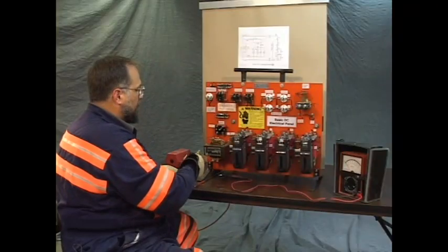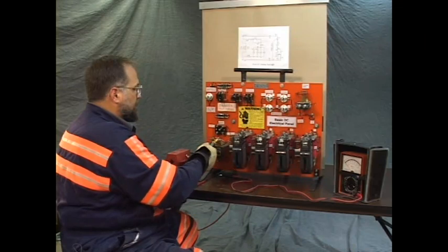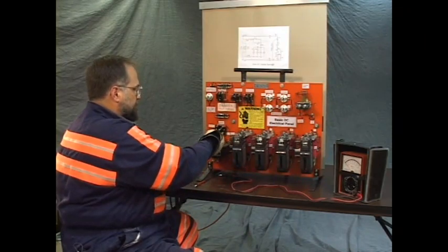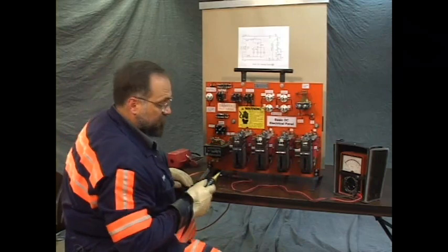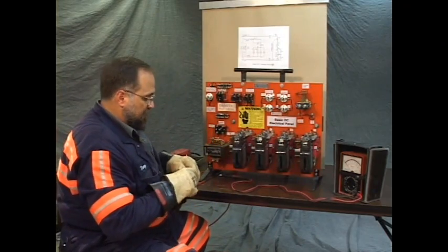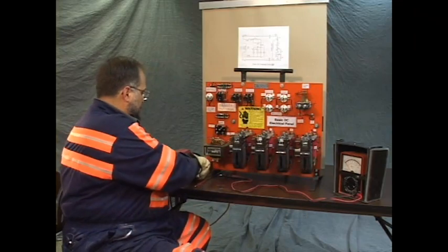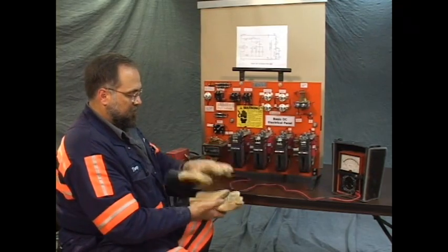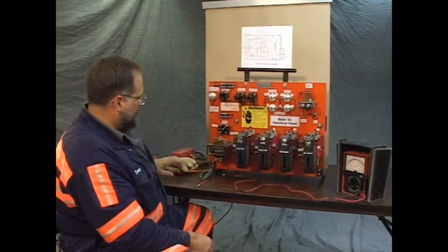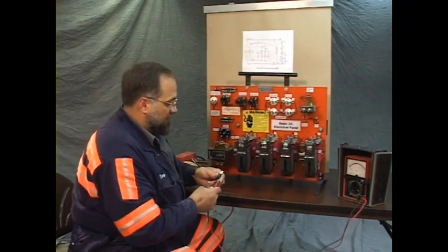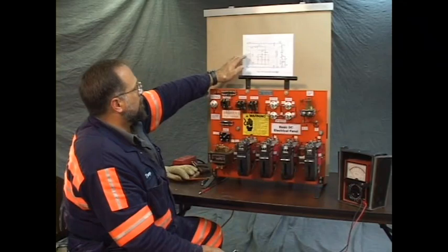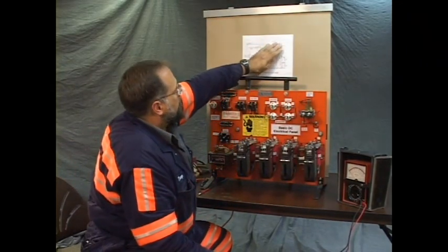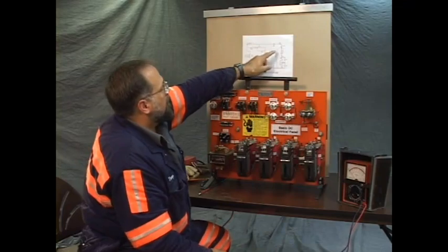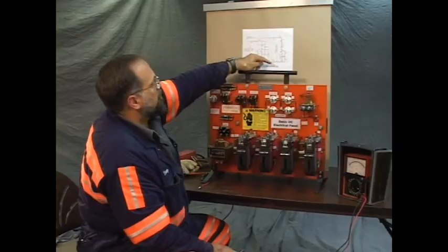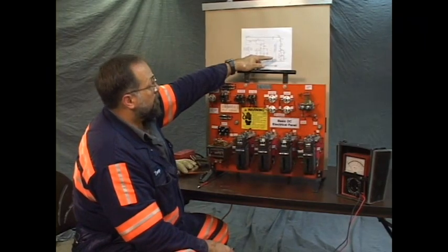This is the incoming part of the power. This is on the secondary of the transformer. It's to be noted that ordinarily these tracers don't detect DC, but it will occasionally chirp on this panel. Take our gloves off. By the symptoms exhibited, we know that this part is working. This part is working, okay? But we have a problem. Our problem lies from here to here, somewhere in that area, but we don't know where. We can narrow it down further.